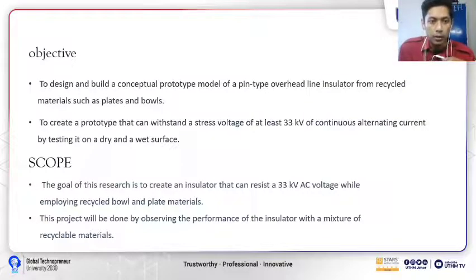So, this project's objective, first, is to design and build a conceptual prototype model of a pin type overhead line insulator from recycled materials such as plates and bowls. Second, to create a prototype that can withstand a stress voltage of at least 33 kV of continuous alternating current by testing it on a dry and a wet surface.